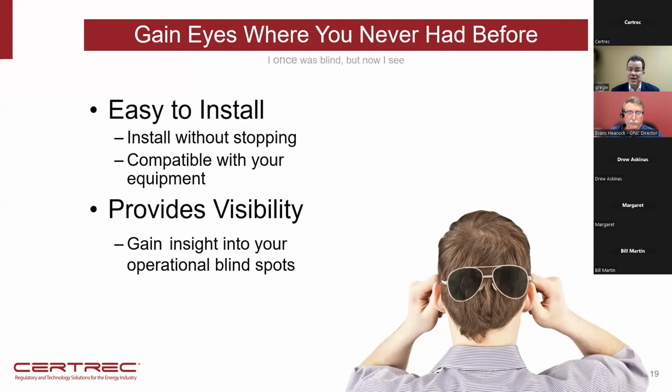And I think, turning it back over to you there, Evans, the real benefit is the ease of installation, especially where we can just connect to existing test switches or test blocks, then there's no wiring at all. If we're installing directly on a panel, then we'll still use our split core CTs, but then we use a voltage cable, and then that provides the visibility.